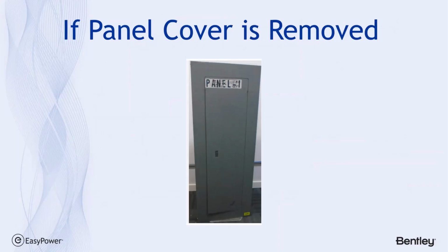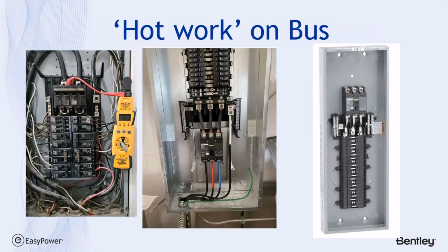So just for clarification's sake, if you're going to remove the cover and work on the bus while it's hot, there's 3 different examples. And obviously this is a single phase domicile or domestic installation, but it illustrates the point. If I'm looking at the incoming connectors to the main, if I can see the metal to that incoming breaker, here we have a bottom fed and a top fed, and in all 3 there's bare conductors, and I'm going to be working on this bus on the other side of that breaker. There's nothing to protect me from an arc initiating on either side of the main, and I'd be in the firing line.